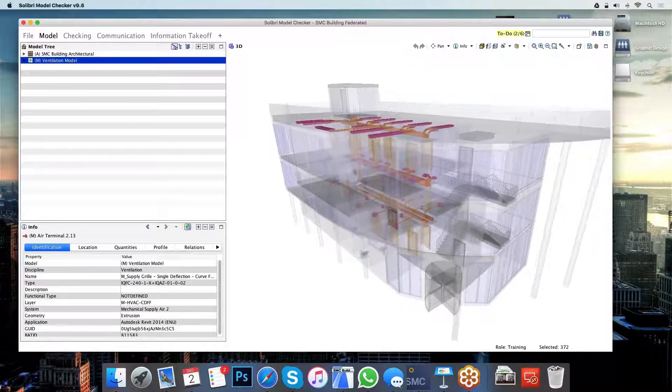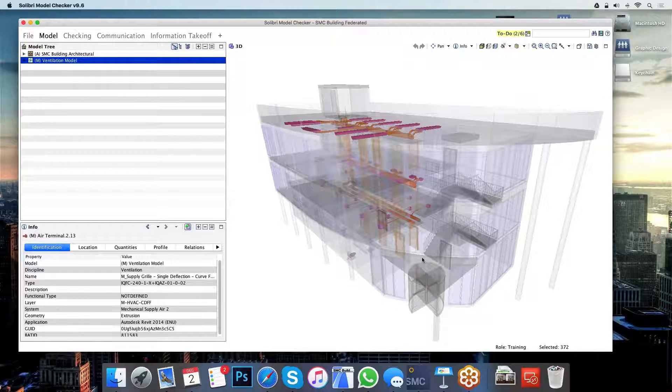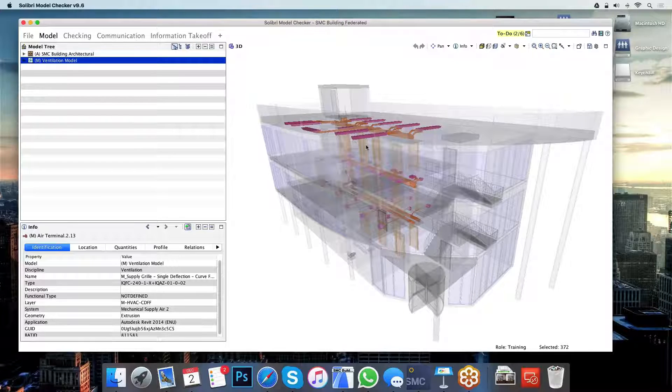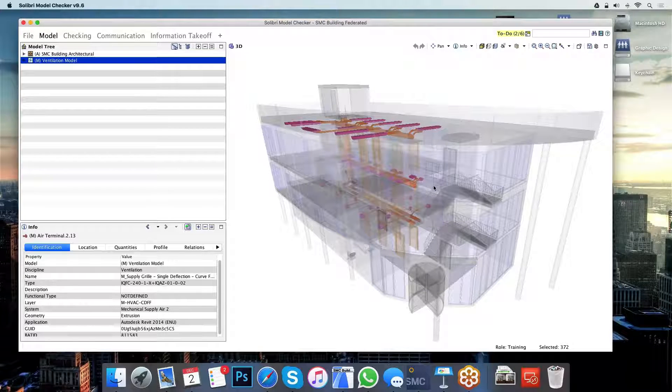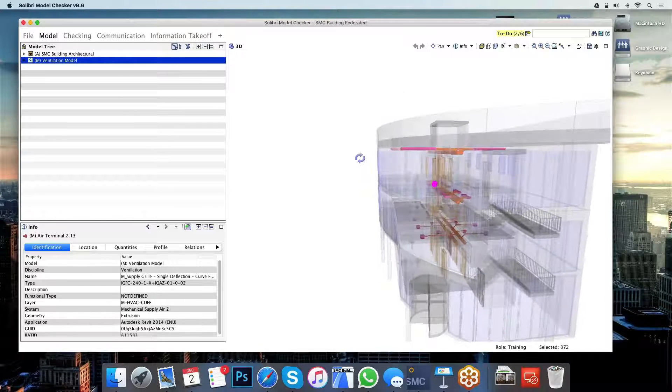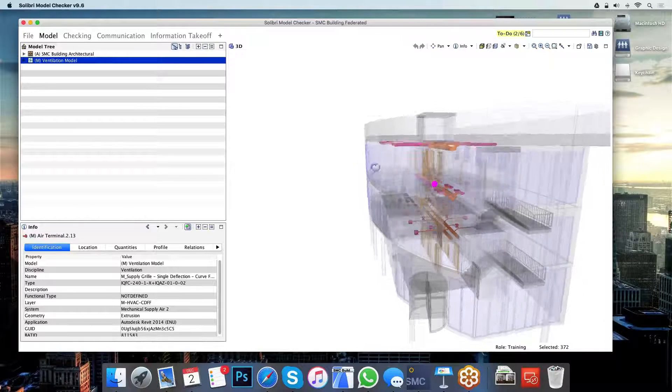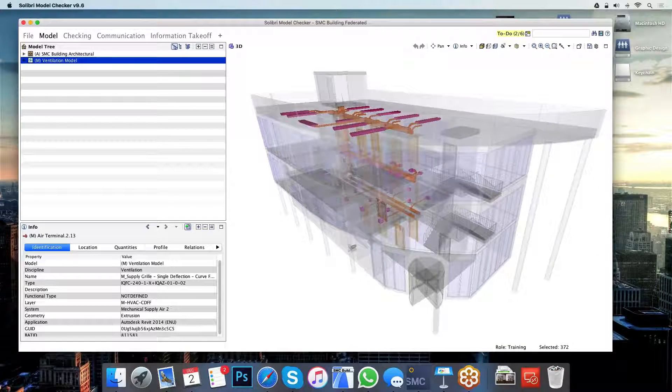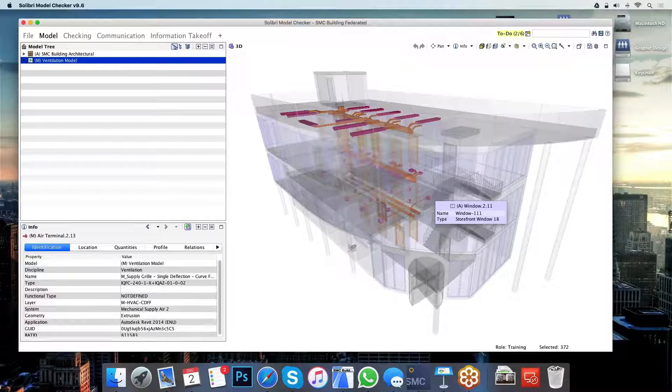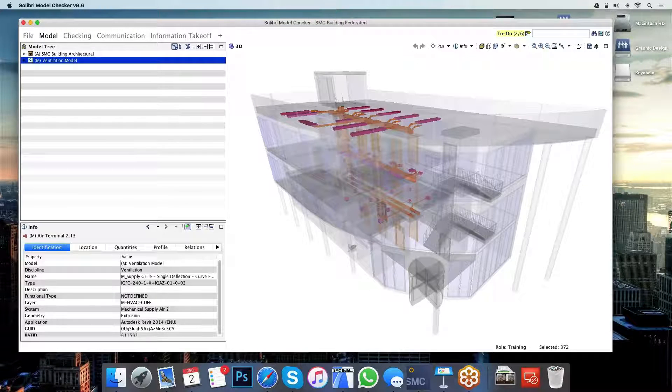This isn't only just for understanding the design. It's a great tool for that too. However, it is a preliminary check too. Because if I have now noticed that there are ducts protruding through the facade in this building, I can immediately flag that up as an issue that will need to be fixed before the design can actually progress on to further stages.